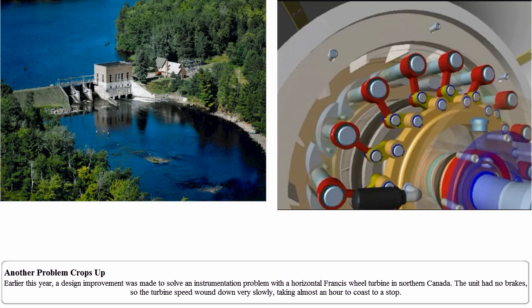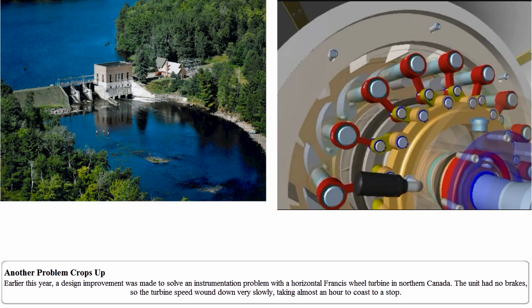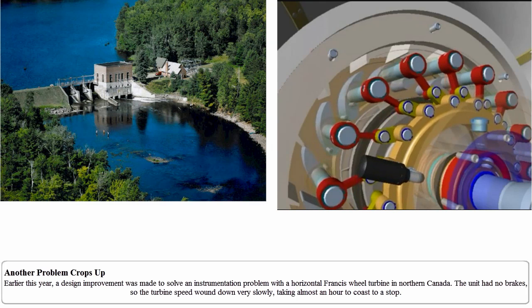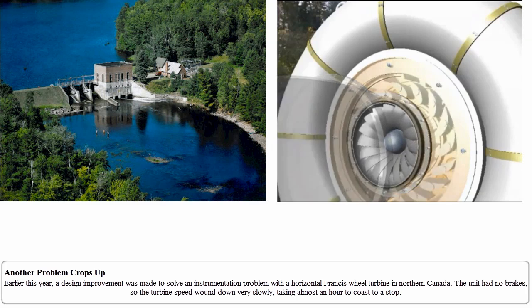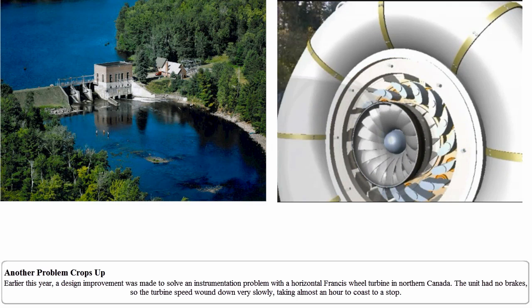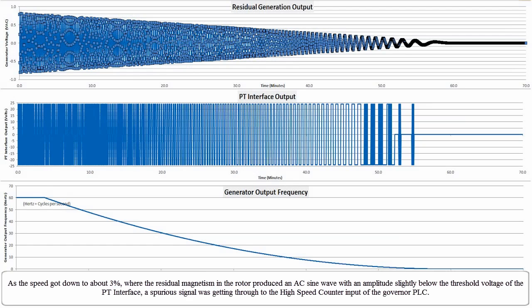Earlier this year, a design improvement was made to solve an instrumentation problem with a horizontal Francis wheel turbine in northern Canada. The unit had no brakes, so the turbine speed wound down very slowly, taking almost an hour to coast to a stop. As the speed got down to about 3%, where the residual magnetism in the rotor produced an AC sine wave with an amplitude slightly below the threshold voltage of the PT interface, a spurious signal was getting through to the high-speed counter input of the governor PLC.